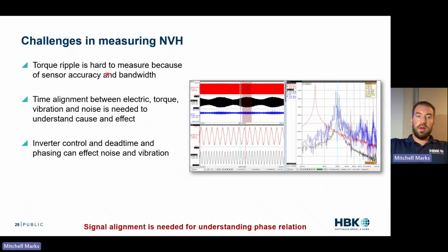Again, I showed this image earlier, but torque ripple is hard to measure because of sensor accuracy and bandwidth. Time alignment between electric torque and vibrations is needed to understand cause and effect. If I change my inverter control, does my torque change? Does my vibration change? And then inverter control and dead time and phasing can affect noise and vibration. So again, we want to understand these things. We want to understand when voltage, when current, when torque, when vibration, how these all correlate together. So you need a common timestamp, you need signal alignment, and then you can start doing your analysis with confidence.